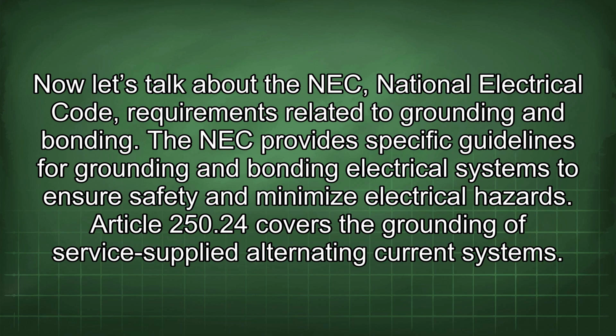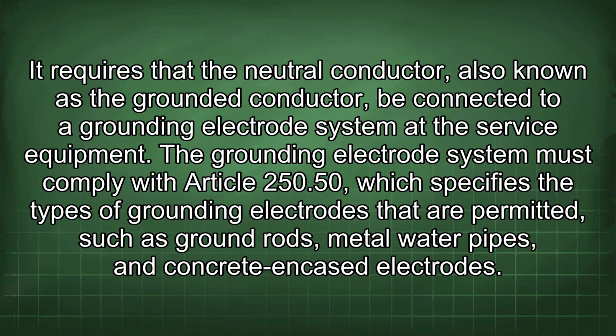Now let's talk about the NEC, National Electrical Code, requirements related to grounding and bonding. The NEC provides specific guidelines for grounding and bonding electrical systems to ensure safety and minimize electrical hazards. Article 250.24 covers the grounding of service-supplied alternating current systems. It requires that the neutral conductor, also known as the grounded conductor, be connected to a grounding electrode system at the service equipment. The grounding electrode system must comply with Article 250.50, which specifies the types of grounding electrodes that are permitted, such as ground rods, metal water pipes, and concrete encased electrodes.